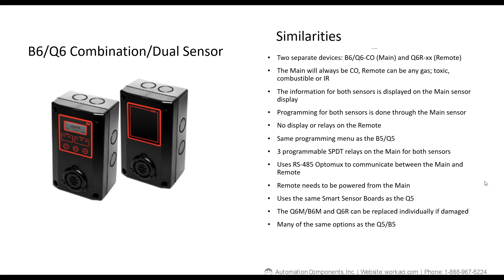Now, Mike brought up earlier that one of the fast-growing applications that we have is boiler rooms. So you could get a combination sensor in CO and methane, so that CO would be mounted at breathing height, 4 to 6 feet off the floor, and that methane would then be mounted up near the ceiling, where that methane gas would accumulate if there was a leak. Correct. Yep. Good point. So, all right.